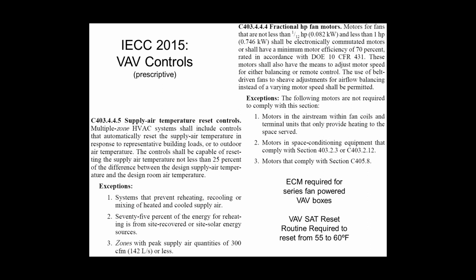You have to do supply air temperature reset on VAV systems, right? This basically means you can't run it at 55-degree discharge air all the time. You have to reset it by 25% of the difference between the supply air and the room temperature. So if you have a 55-degree supply air design and you have a 75-degree room temperature, 25% of that would be 5 degrees. Therefore, I have to be able to reset your supply air temperature between 55 and 60 degrees. And depending on what the spaces want, I can go between those two things. You can do that based on building load, which typically means let's look at all the zone temperature readings and see how close they are to their set points. Or you can do it based on something more indirect, like outdoor air temperature, which I would not recommend, but it is allowed by code. I would highly recommend you do it based on what the zones are asking for.